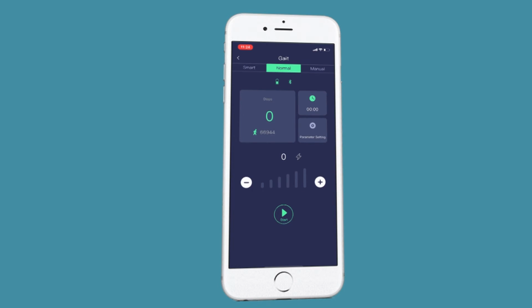And once the parameters are sent, then again, I would hit start, increase the intensity to the appropriate level, and have the patient walk. Again, in all of these, I would have it in audible beat mode as well, so I could hear what is going on as well as observe. So normal mode is a quick way to fine-tune the device after the device has been used in smart mode. Manual mode is good for treatment in a rehab setting.